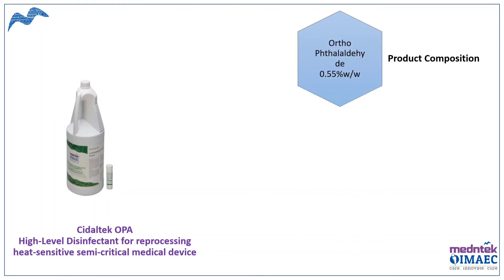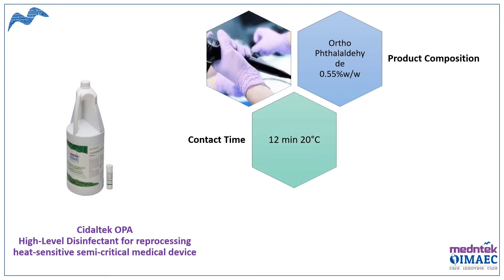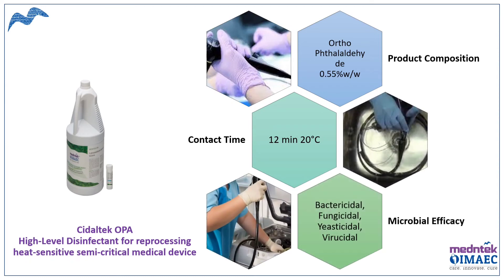A solution provided for high-level disinfection in endoscope reprocessing is Cidaltek OPA. Its chemical composition is Orthophthalaldehyde, and the required contact time is 12 minutes at 20 degrees Celsius. It has broad-spectrum microbial efficacy, being bactericidal, fungicidal, yeasticidal, and virucidal. It is also used for automatic endoscope reprocessing.